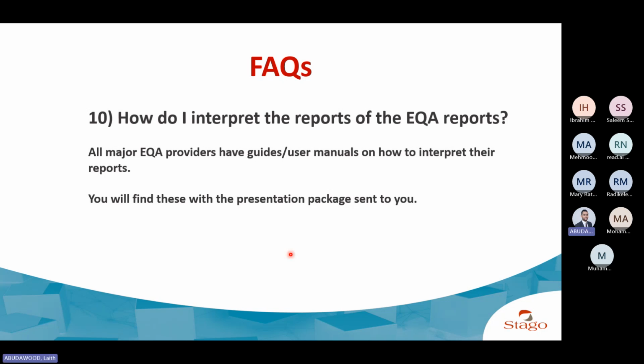How do I interpret the reports of the EQA providers? Now, as I told you in the beginning, the reports generally are simple because usually all I care about is the SDI or the Z-score. If your SDI or Z-score are okay, done, finished. Okay, there's not that much to do.